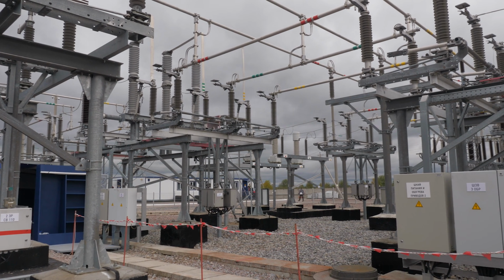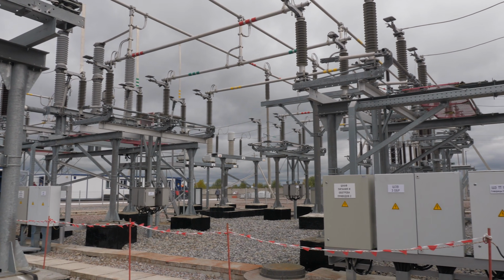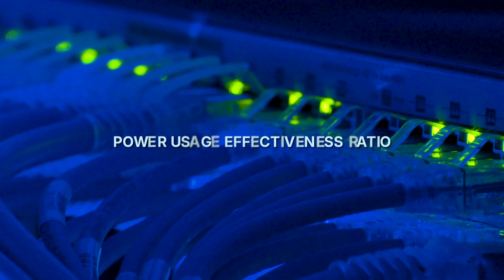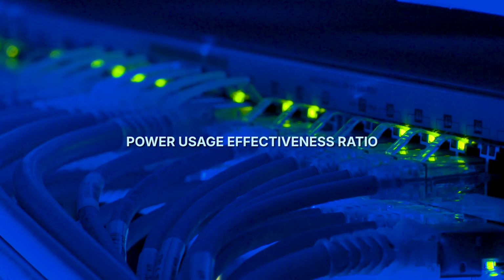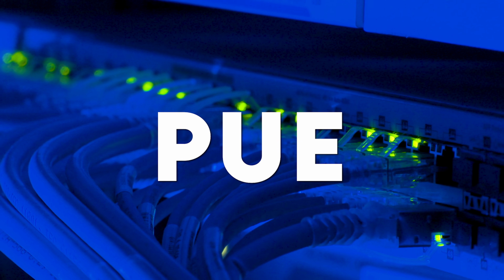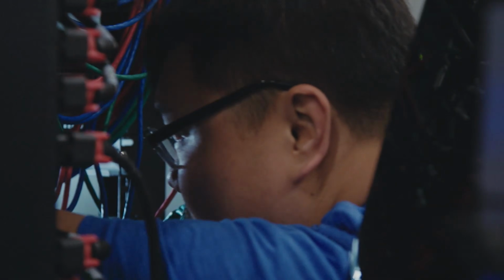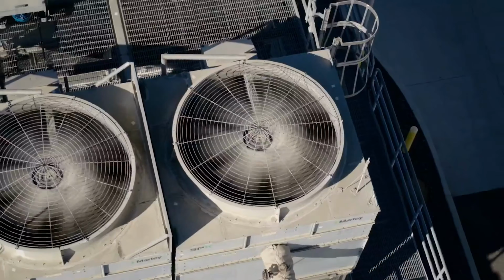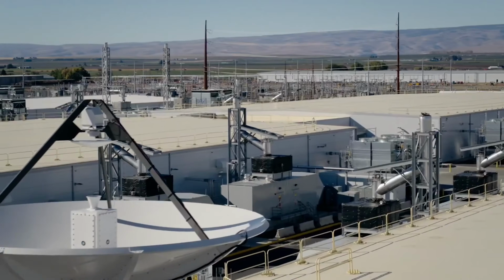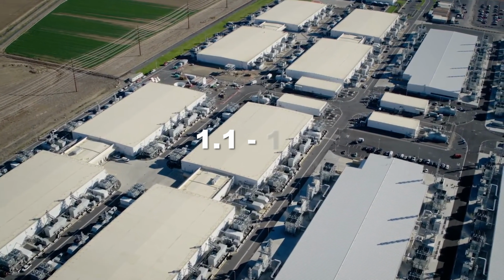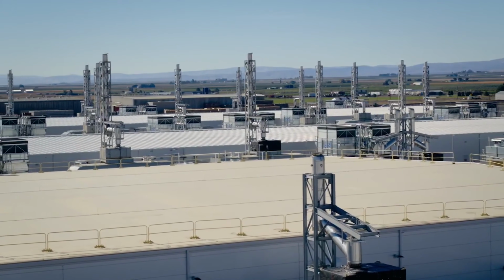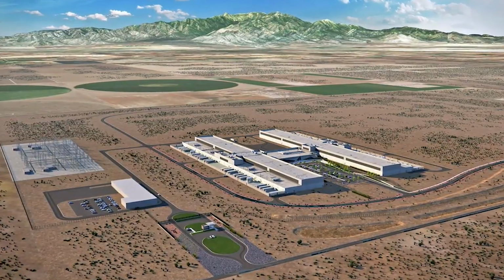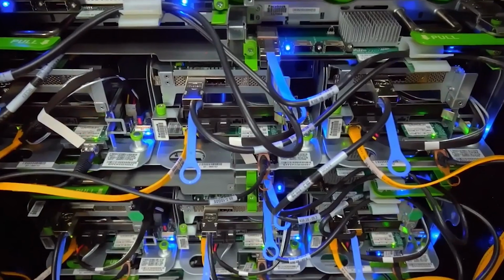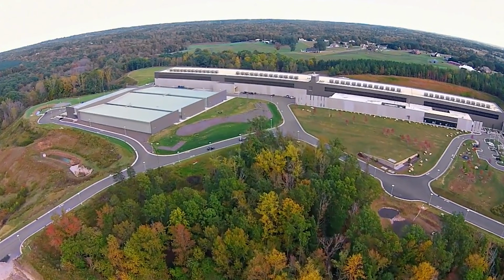Electricity typically represents 40 to 50% of total operating expenses. Your power usage effectiveness ratio, the industry standard metric called PUE, measures how efficiently you use power. A PUE of 1.0 would mean every watt going into the building goes directly into computing. In practice, the best modern facilities achieve PUE ratios around 1.1 to 1.2, meaning 10 to 20% overhead for cooling and infrastructure. Older facilities run 1.5 to 1.8, which is a massive competitive disadvantage when electricity prices rise.